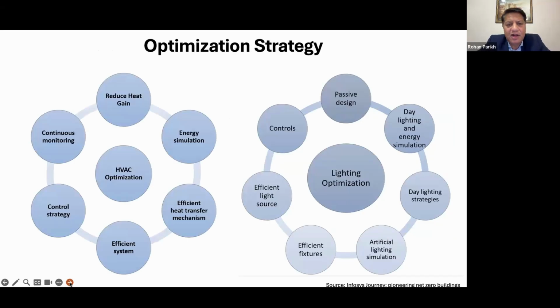We implemented a lot of optimization strategies for lighting and HVAC. The first part was passive design and the daylighting strategies I spoke about. Even the artificial lighting was done using simulation, using the most efficient fixtures. Today 160 lumens per watt is a bare minimum in most buildings, and that's why we're able to achieve 0.3 watts per square foot LPD.